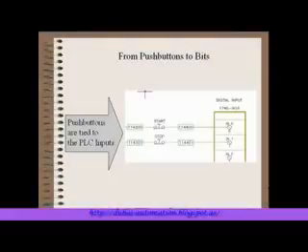So what's the difference between the PLC and the regular hardwired option? Well, with hardwired, you saw we take our push buttons directly to a relay, and it acts directly upon that relay. With the PLC, we have our start button, and it comes into an input card. It's wired directly into cards that interface directly to the processor through a rack or some other means. So both our start and stop push buttons from our previous example come into an input card, and then they can be used and processed, and we'll see that later when we get into the PLC program. They can be manipulated inside the PLC program.